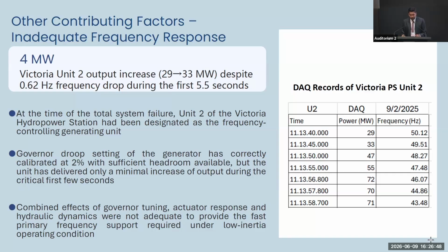Even for this, you can see the DAQ records I have shown here. DAQ means data acquisition records of Victoria Power Plant. It has increased its power from 29 megawatts to 33 megawatts, despite the frequency drop of 0.62 hertz during the first 5.5 seconds. So that indicates the combined effect of the governor tuning, actuator response, and hydraulic dynamics were not adequate to provide the fast primary frequency support required under the prevailing low inertia operating condition. The desired outcome has not been given by that frequency controlling plant.